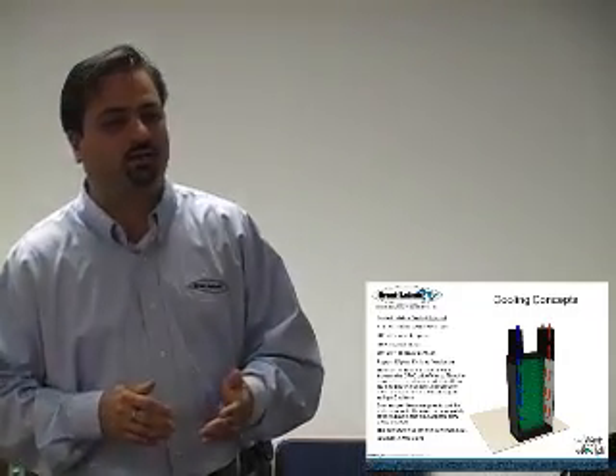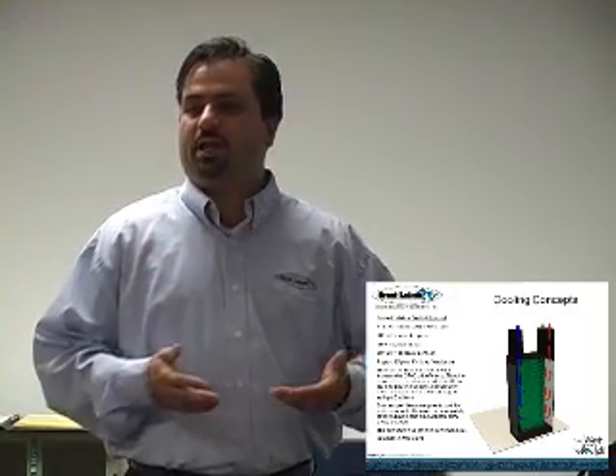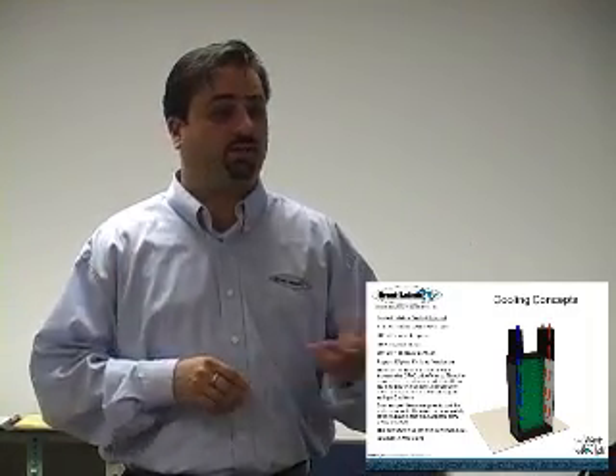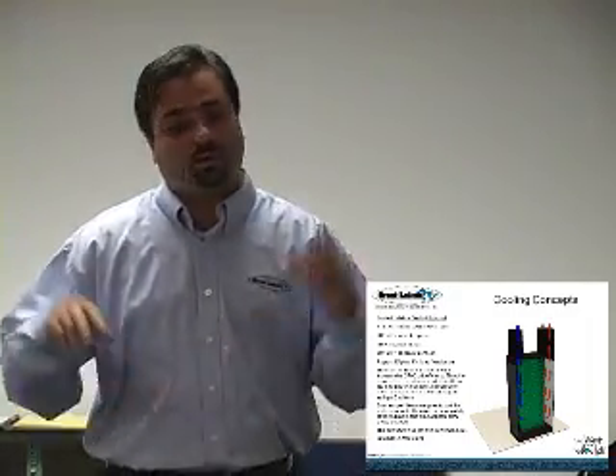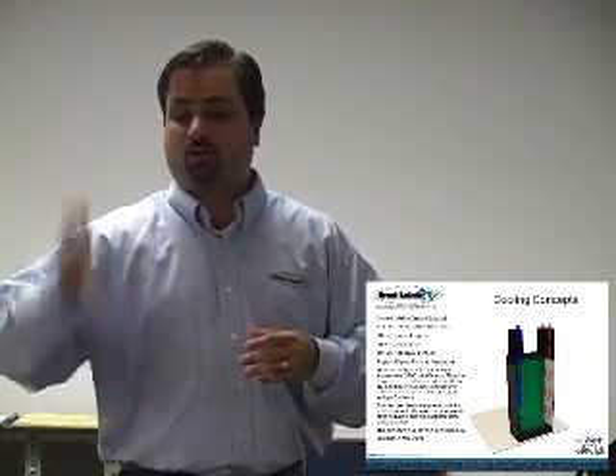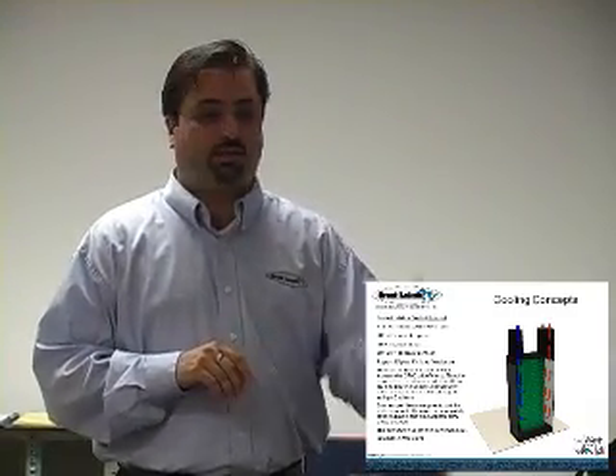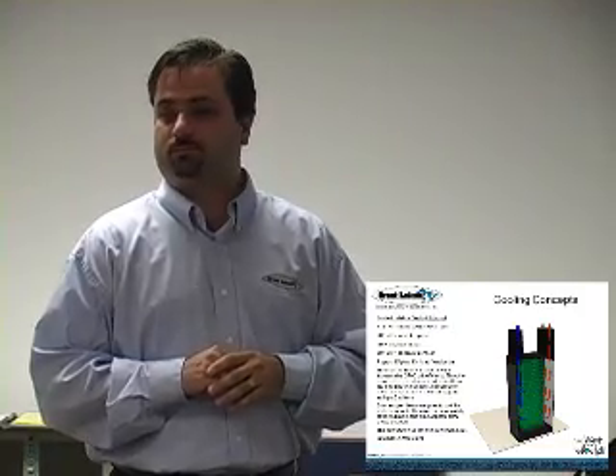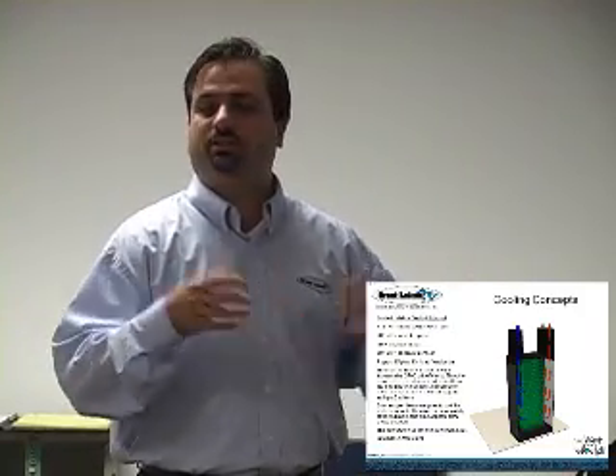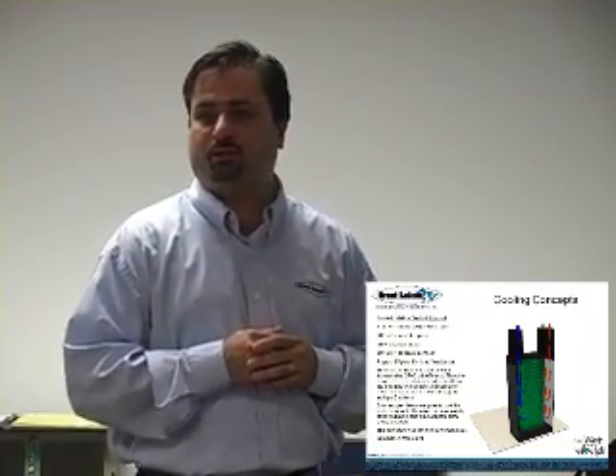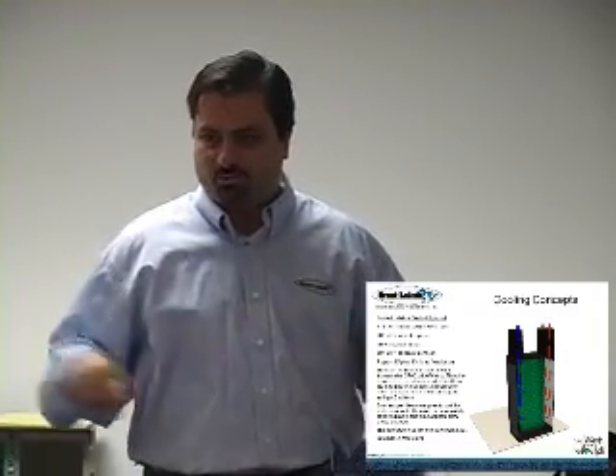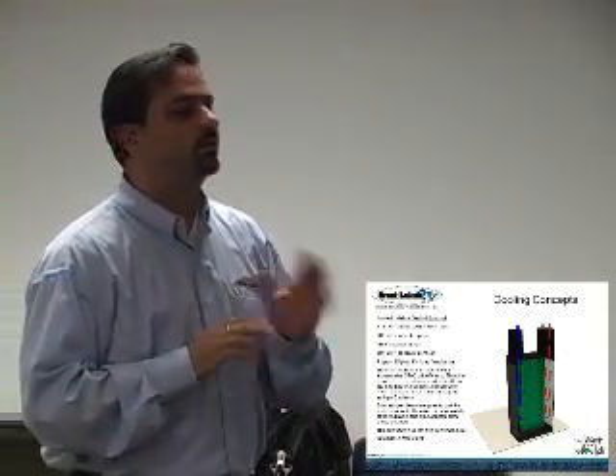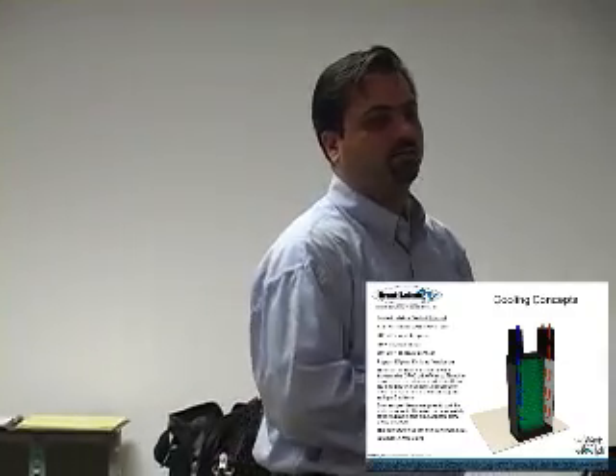But if it's ducted correctly, you can actually gain that efficiency and maybe even start turning down. We've seen some CFD models where they actually turned off 2 CRAC units completely and gained cooling because of how it was managed and ducted properly, rather than having short circuits and heat recirculation. It's atrocious, the methodology out there.